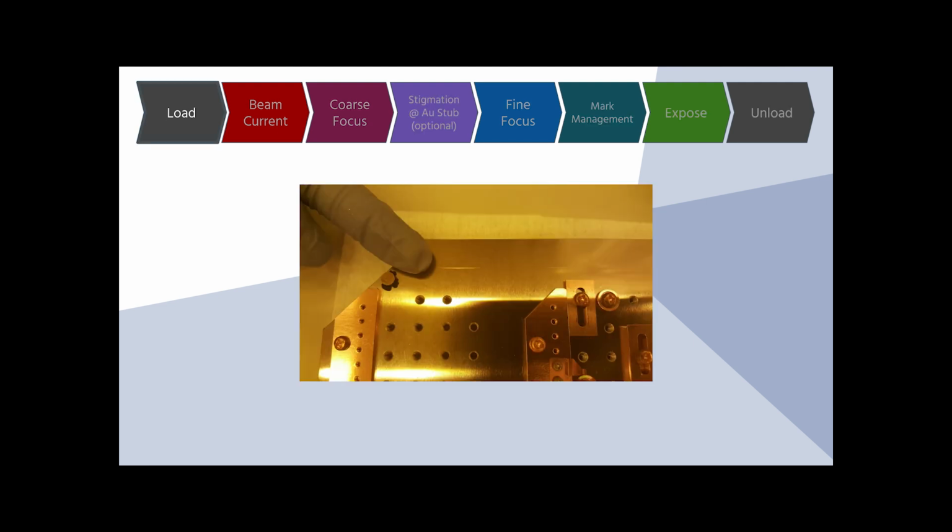Loading a sample into either system is where we have the greatest risk of hardware damage. In the past, a lab member inserted a pallet into the chamber without the stage in place. In order to fix this, we had to do a full vent of the main chamber, which took the system down for an extended period of time.